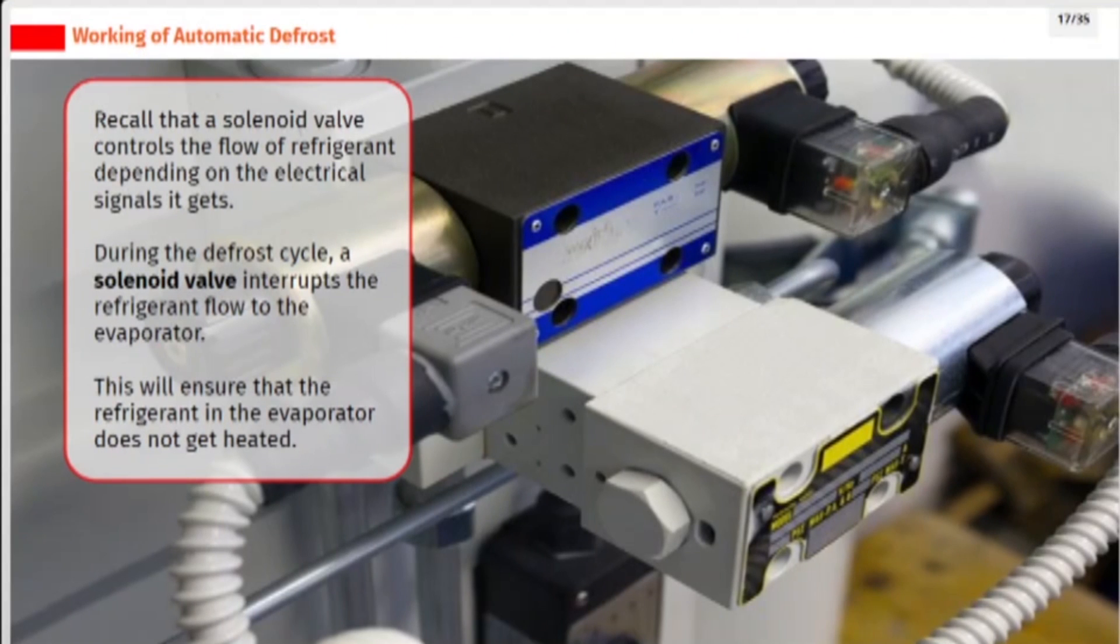Recall that a solenoid valve controls the flow of refrigerant depending on the electrical signals it gets. During the defrost cycle, a solenoid valve interrupts the refrigerant flow to the evaporator. This will ensure that the refrigerant in the evaporator does not get heated.